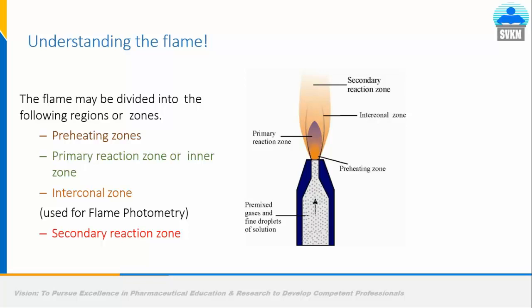Now let's understand the flame itself. The flame can be divided into various zones: the pre-heating zone, primary reaction zone or inner zone, interconal zone — used for flame photometry — and the secondary reaction zone. Observing a flame, we must understand which area to focus on for a particular protocol. The interconal zone, just above the blue part, is the site where we focus in flame photometry.